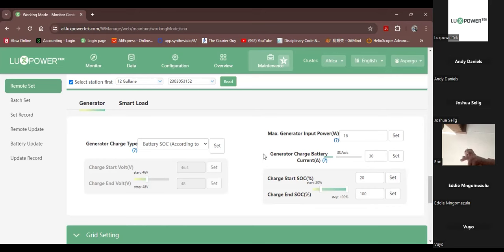If there is PV available, then the PV will charge the battery only. PV will never take load when the generator relay is open. And we do that for a very, very simple and important reason. It's so that the generator cannot receive any leak current, and we will simply damage the alternator by doing that. So we don't allow that at all.